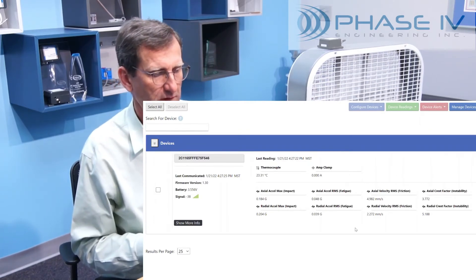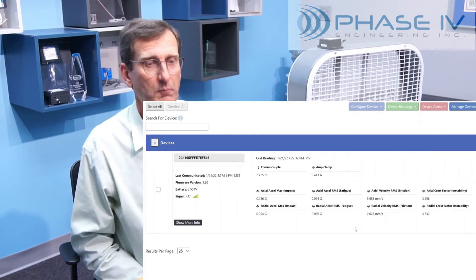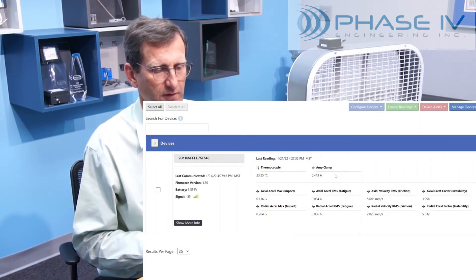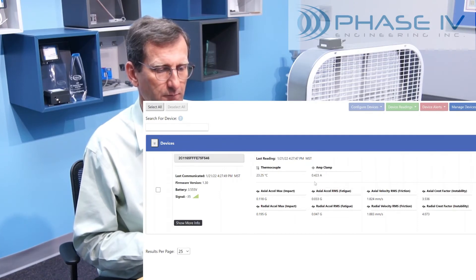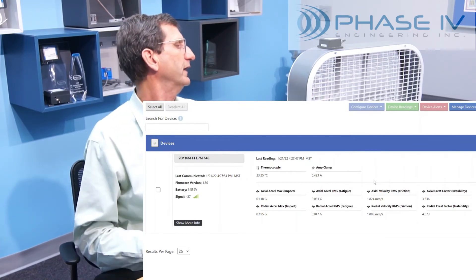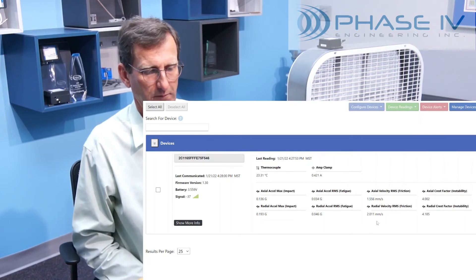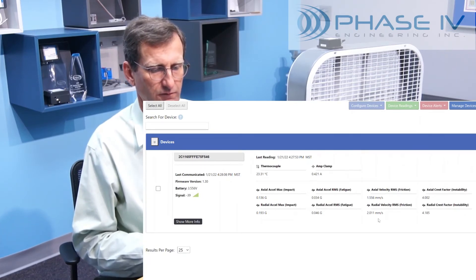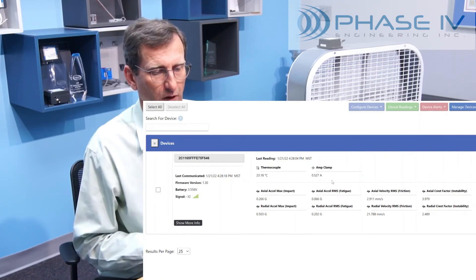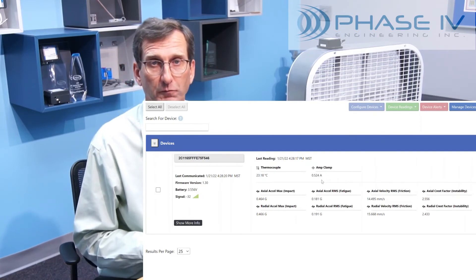We've got the fan on low speed, and we have the device node transmitting about every five seconds — a lot more than you would normally do in a production plant, but for demonstrations it works well. You can see now that the amp clamp has bumped up to about 0.42 amps, and you can see the vibration parameters starting to change. Now bumping it up to high speed, some of the vibration readings jump quite a bit — for instance, this one went from 2.011 and jumped to 21. Our amp clamp has jumped up to 0.52, giving you a feel for the sensitivity of the system.